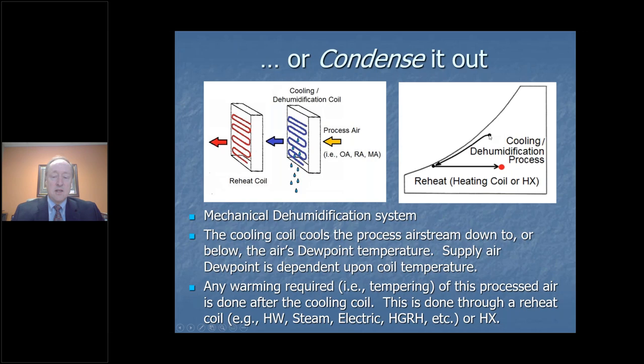This is what that process looks like on the psych chart. We're moving from here to that same red state point from the previous slide, but it goes in an opposite direction. We begin cooling it down all the way to saturation, where the apparatus dew point of the coils is. And then from that point, we might need to do some reheat in order to get it to this point right here.